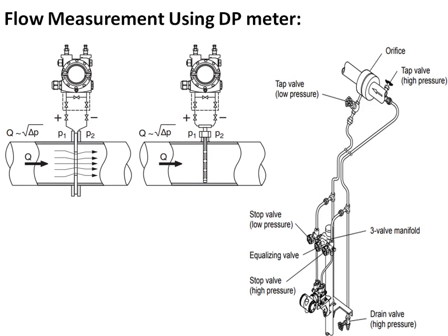For flow measurement using the DP transmitter, the different configurations shown on the left side illustrate flow measurement using an orifice and a pitot tube. The orifice and pitot tube cause a pressure drop. The difference in pressure is measured by the DP transmitter, which is proportional to the square root of delta P.